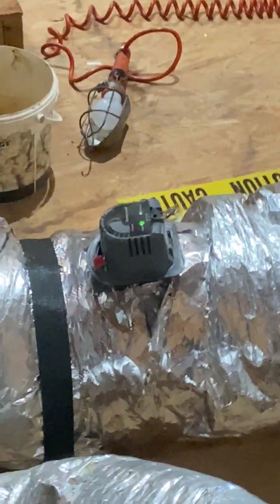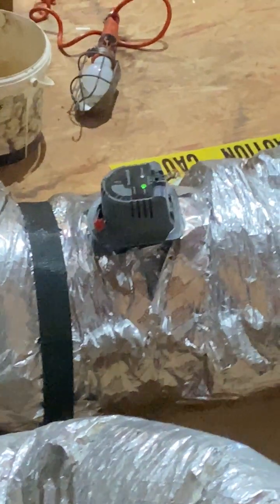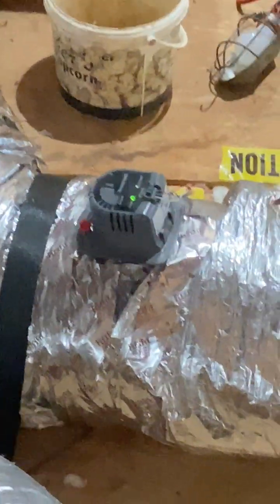You saw them. Okay. The zone control valves, if you do it yourself, just make sure when you put the motor head on that you're properly aligned with the inside open and closed. Now on the zone control valves, you have the same sort of adjustment possible with it that you had with the one I showed you, the old style, and that is you can control what fully closed means. And here on this particular one, you see the red lever here at the top. There's markings on it that says you can set it for position 1, 2, 3. This has a needle in it which moves. This is fully closed. This is fully open. And by using this red lever, you can adjust how much fully closed you get.